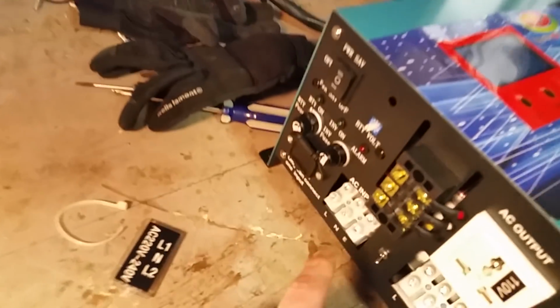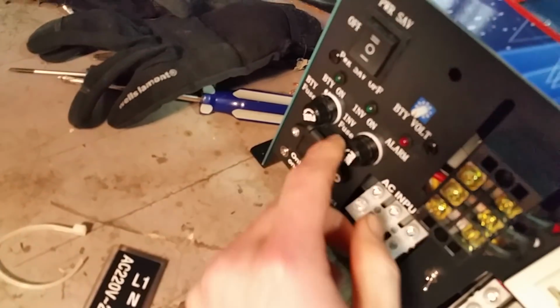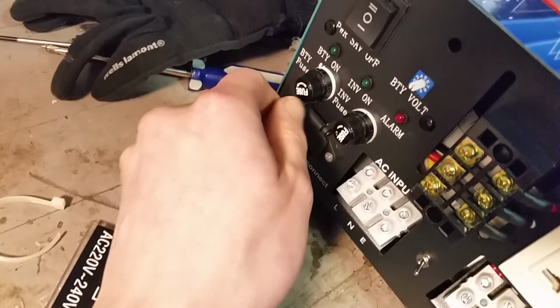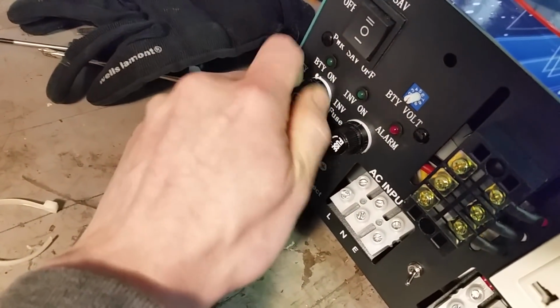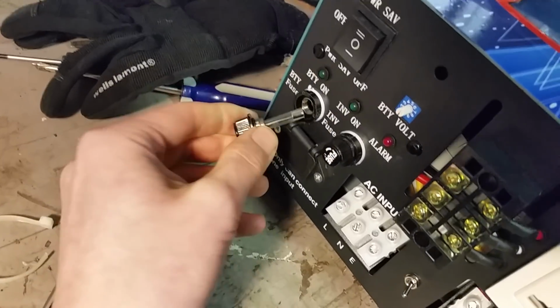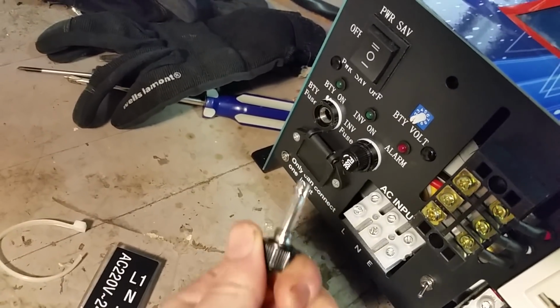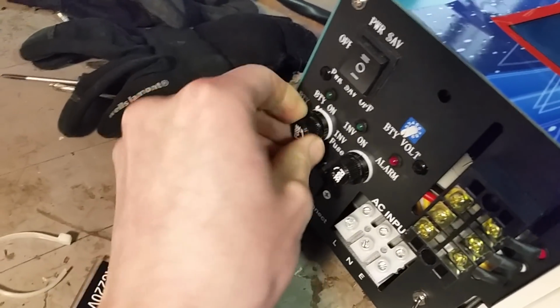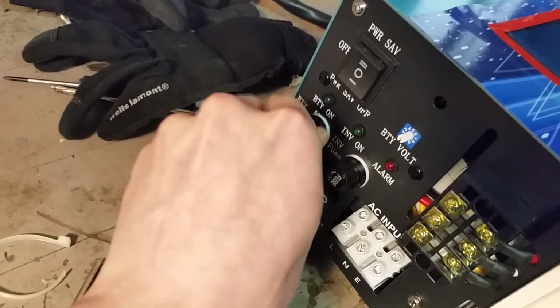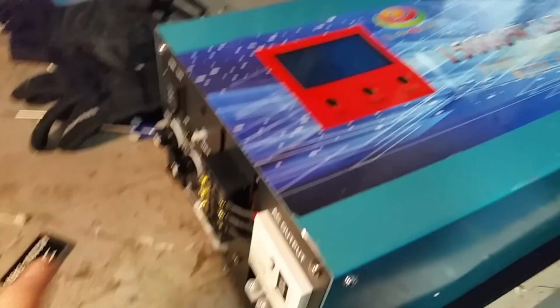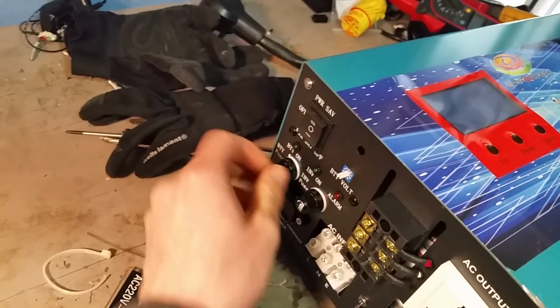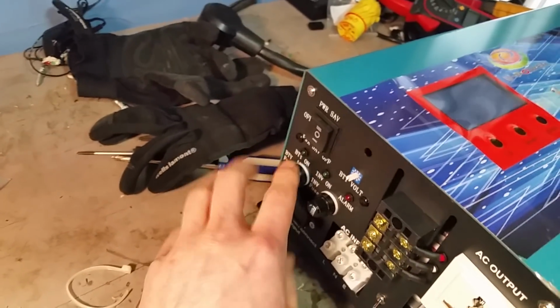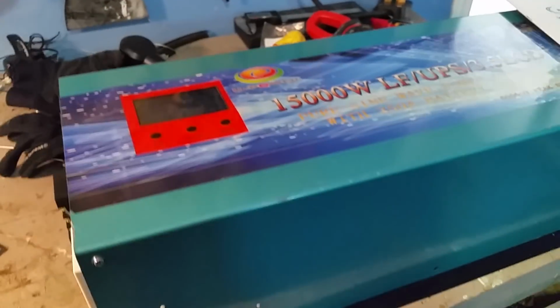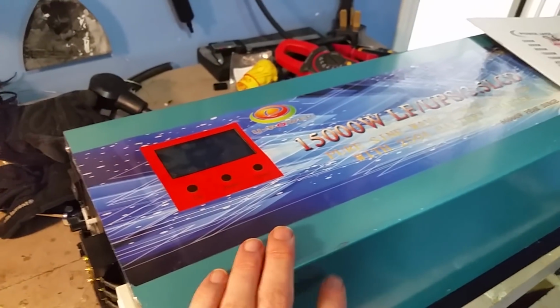The other thing that's really obvious is these fuses, these are 20 amp fuses. How do you expect 69 amps to go through a 20 amp fuse? It's just ludicrous why they would expect that. Yes, momentarily for a few seconds, I get that, that's fine, a slow blow fuse could probably handle 69 amps for a few seconds without blowing. But that's not what I'm talking about, I'm talking about continuous load.